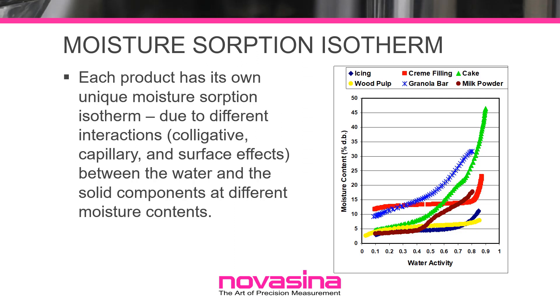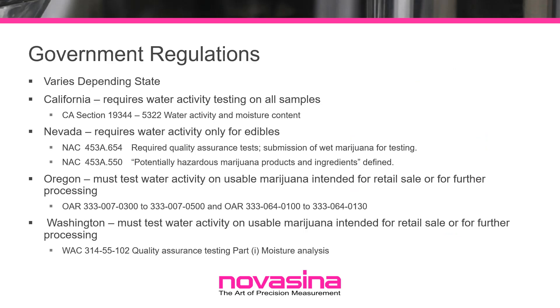Water activity is an intensive property that provides the energy of the water in a system. Moisture content is an extensive property that determines the amount of moisture in a product. Water activity and moisture content, while related, are not the same measurement. Moisture content is typically determined through loss on drying as the difference in weight between a wet and dried sample. While useful as a measurement of purity and a standard of identity, moisture content does not correlate as well as water activity with microbial growth, chemical stability, or physical stability.